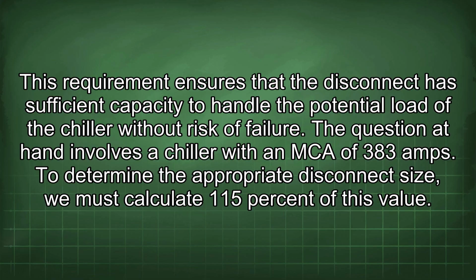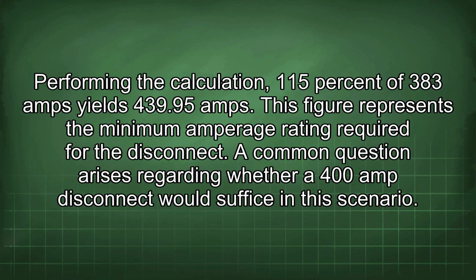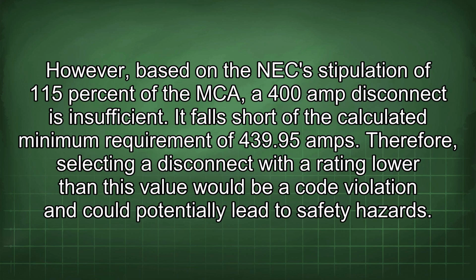To determine the appropriate disconnect size, we must calculate 115% of this value. Performing the calculation, 115% of 383 amps yields 439.95 amps. This figure represents the minimum amperage rating required for the disconnect. A common question arises regarding whether our 400 amp disconnect would suffice in this scenario. However, based on the NEC stipulation of 115% of the MCA, a 400 amp disconnect is insufficient. It falls short of the calculated minimum requirement of 439.95 amps. Therefore, selecting a disconnect with a rating lower than this value would be a code violation and could potentially lead to safety hazards.